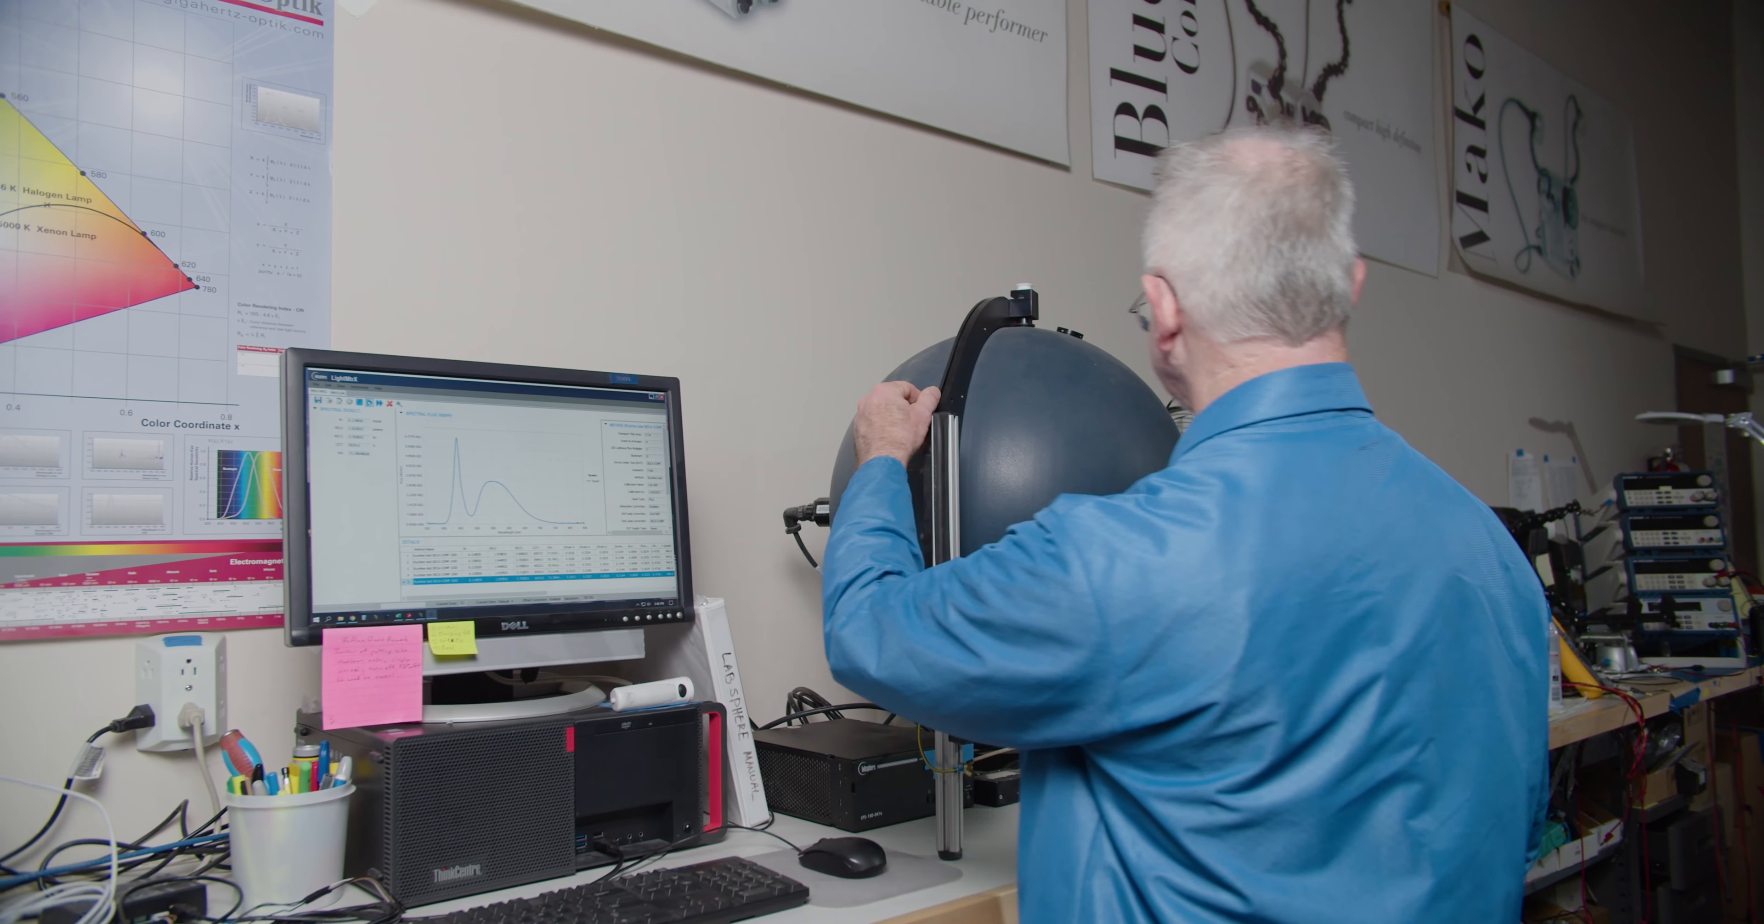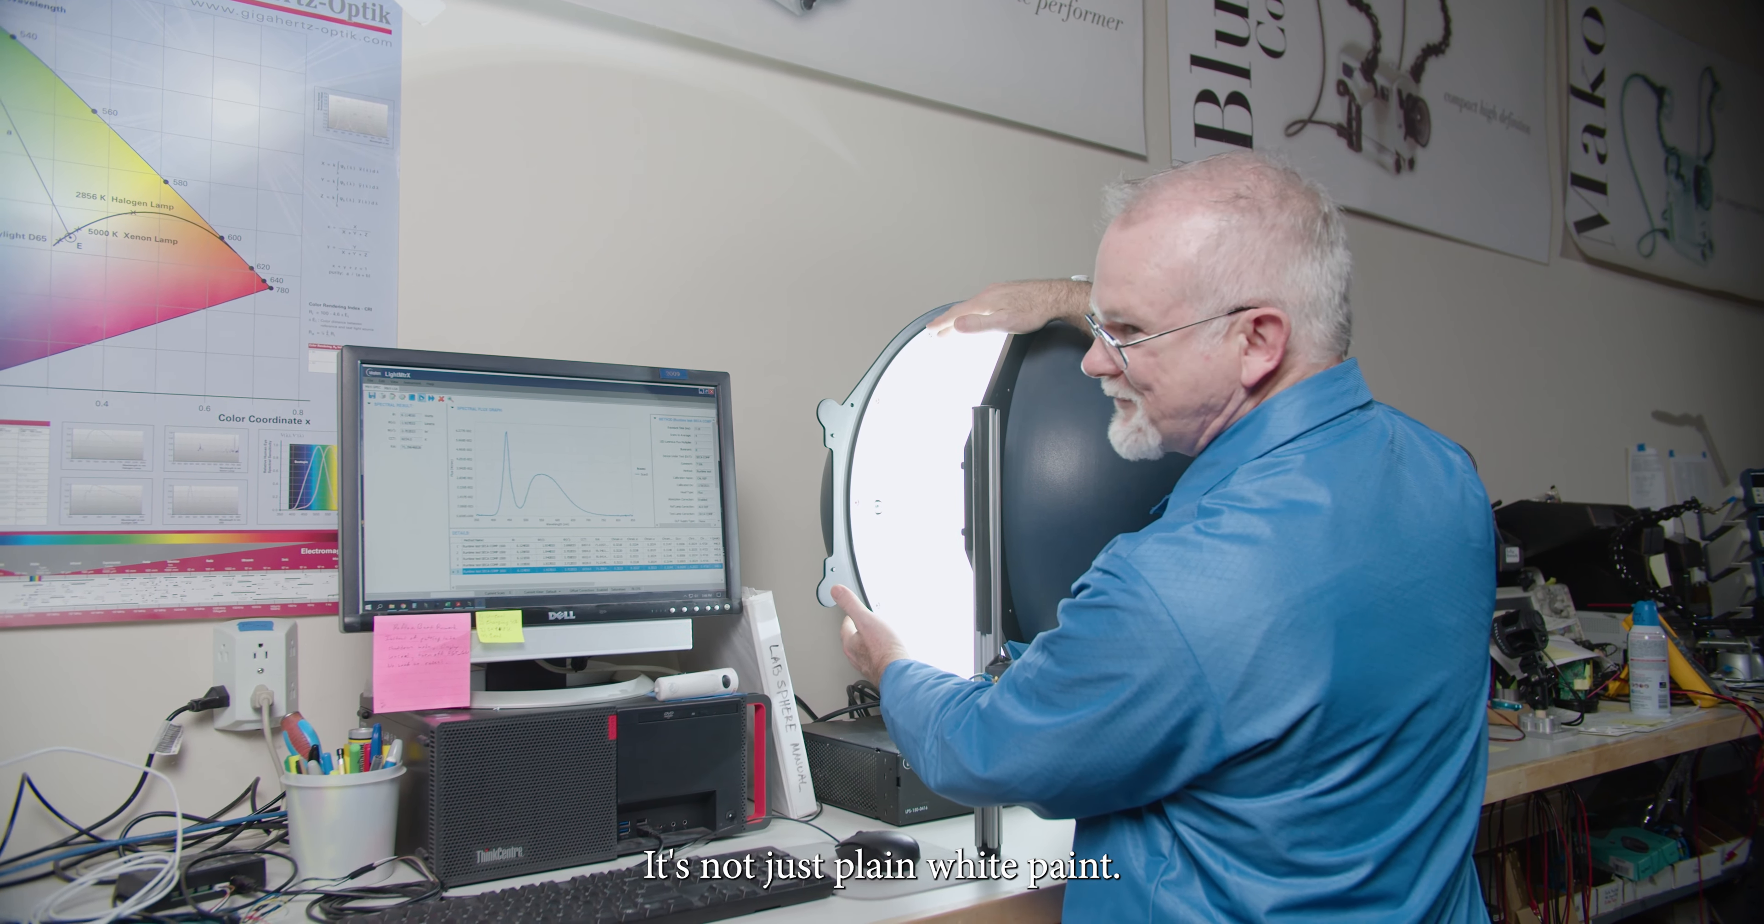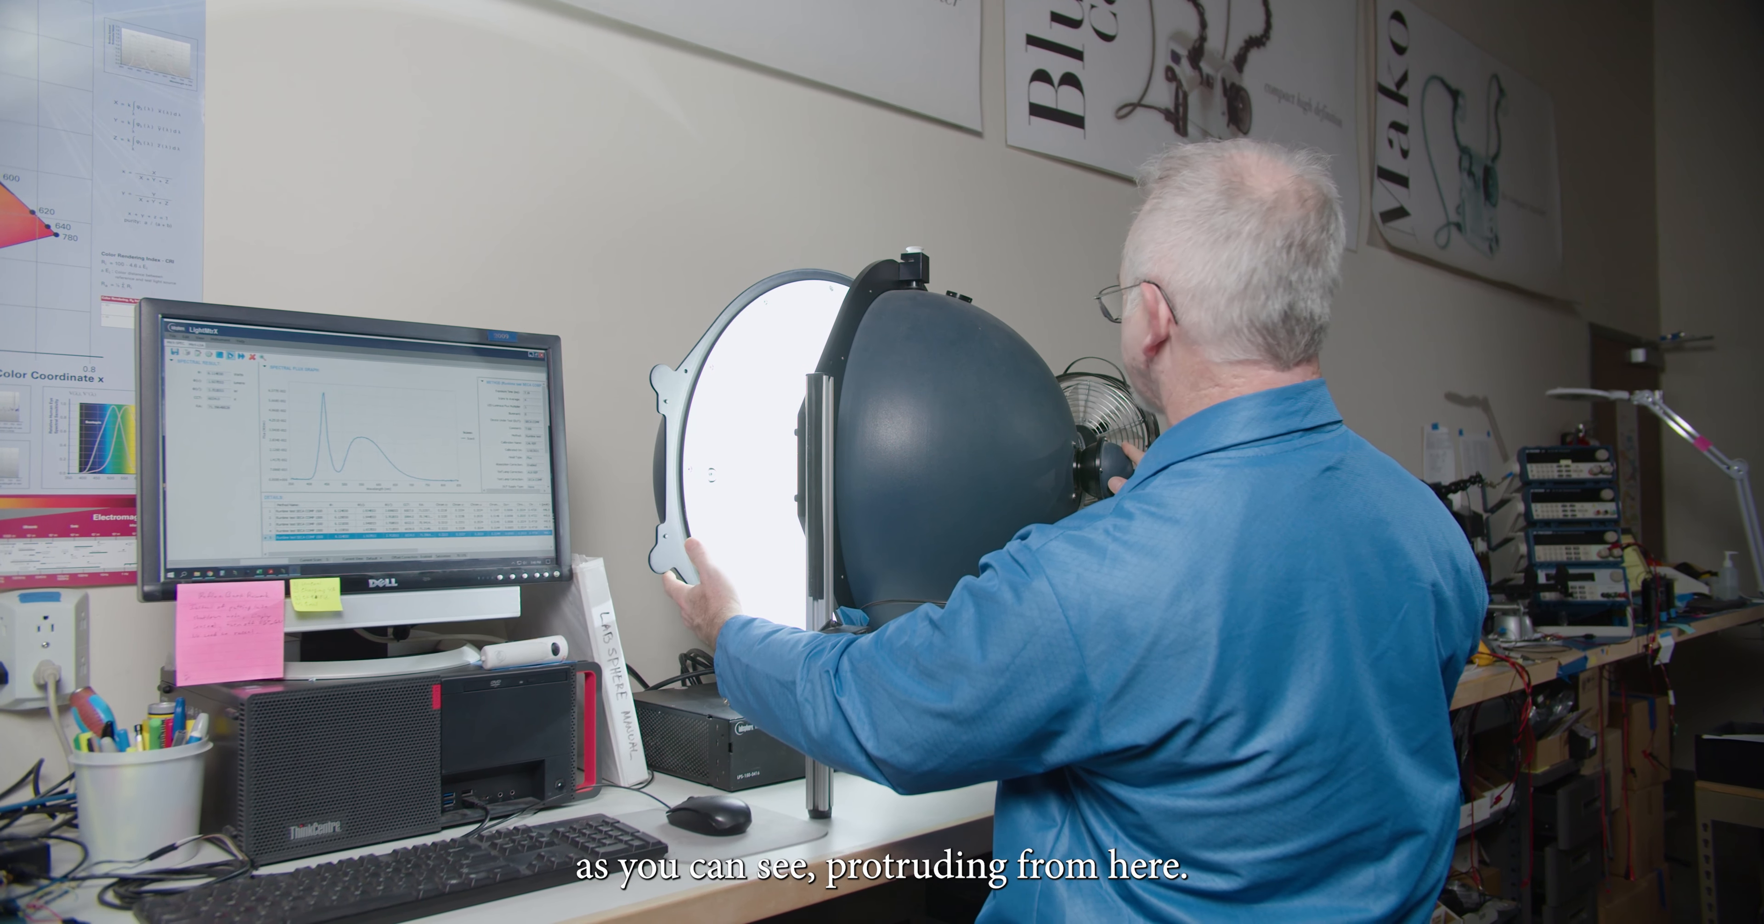Let's take a peek inside. So all of the light bounces around inside this sphere. It has a specially reflective coating. It's not just plain white paint. And then there's a calibration lamp that you see in the back there. And there's a sensor on this other side that you can see protruding from here.